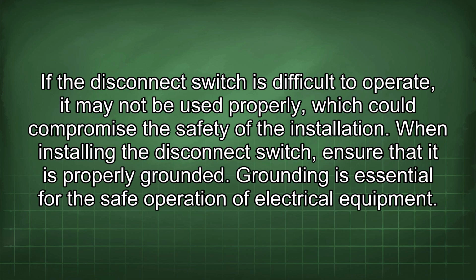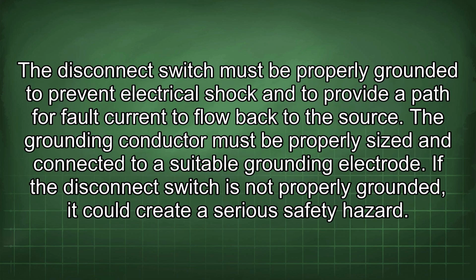When installing the disconnect switch, ensure that it is properly grounded. Grounding is essential for the safe operation of electrical equipment. The disconnect switch must be properly grounded to prevent electrical shock and to provide a path for fault current to flow back to the source.